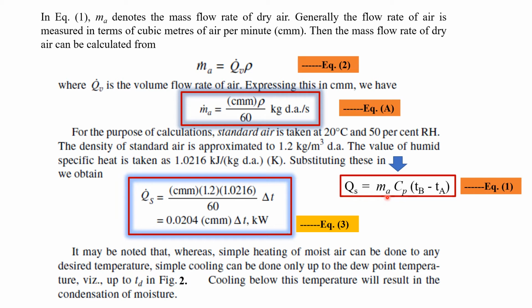So what we are going to do is insert the value of Ma from equation number 1, and also insert the value of Cp here. So that is going to give us cmm into rho, density, which is 1.2 divided by 60, and Cp, the humid specific heat, is taken as 1.0216. So it is going to be cmm into 1.2 multiplied by 1.0216 divided by 60, and of course Tb minus Ta, or Ta minus Tb, is nothing but delta T. So when we look at the unit of this entire expression, it simplifies to 0.0204 cmm into delta T, and the unit is very important, it is now in kilowatt.